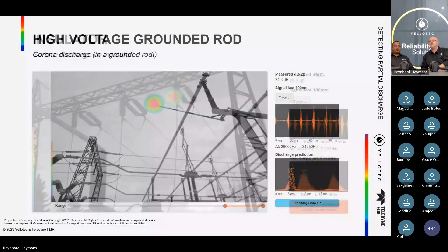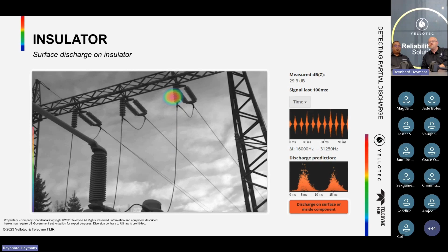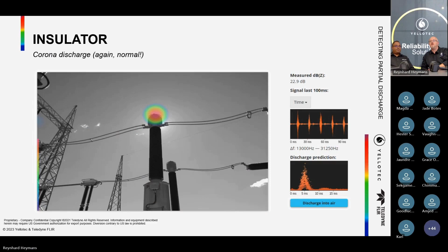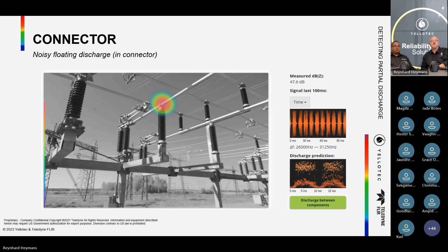Okay, here are some other examples of discharge. Again, insulator. Take note of the severity at the bottom. You know, it tells you how soon you actually need to do the job or to do the repair, which I think helps the criticality point of view. How often have you seen discharge on a connector or contactor? I mean, this could create hotspots, right? Eventually, yeah. It could create hotspots. Again, critical breakdown. Another connector fault.